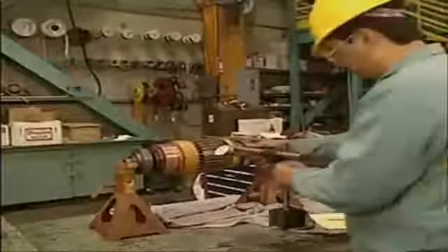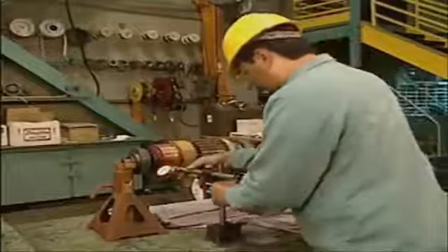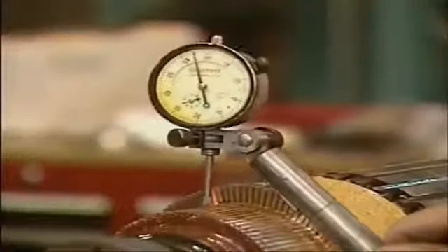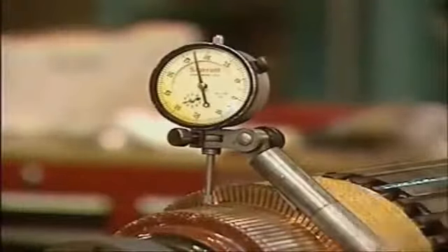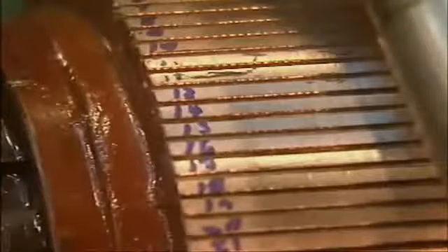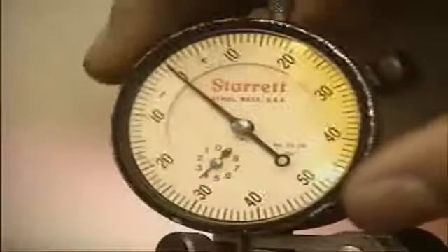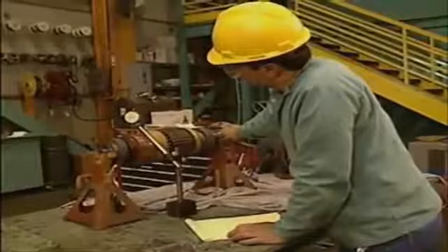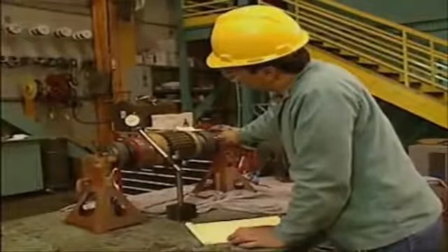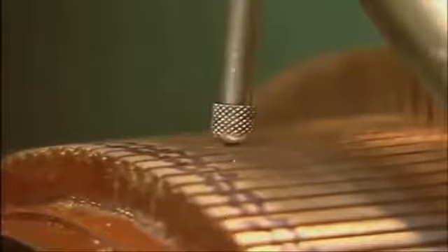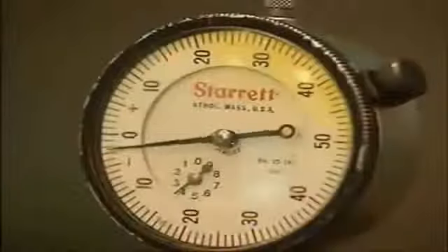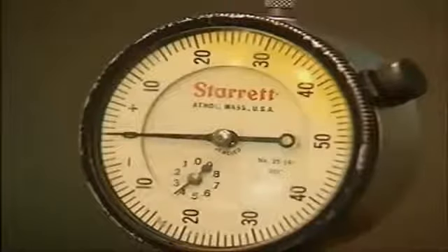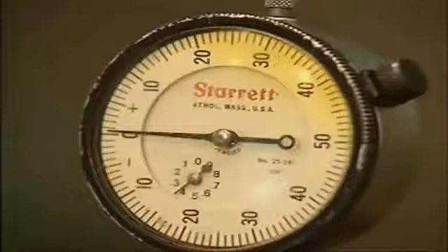A dial indicator can be used to check the commutator for trueness. In other words, to make sure that all of the segments are level with each other. Each segment is numbered to identify them, and then checked with the indicator actually on each segment. The armature should be rotated very slowly, and the readings should be recorded accurately.